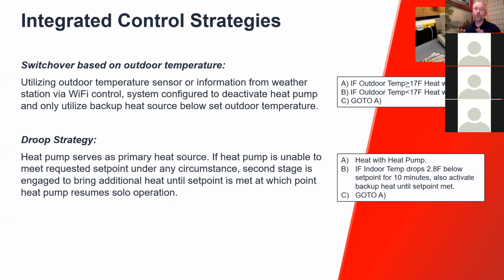Okay, so then the droop strategy is where you've got the heat pump running, and if there's any circumstance where the heat pump is unable to keep up for a particular period of time, and different systems are going to have different variables set into this, like a specific droop amount, like how far below a set point it is, and how long it's below that set point that the system senses that it's unable to keep up, before it triggers that backup to come on.